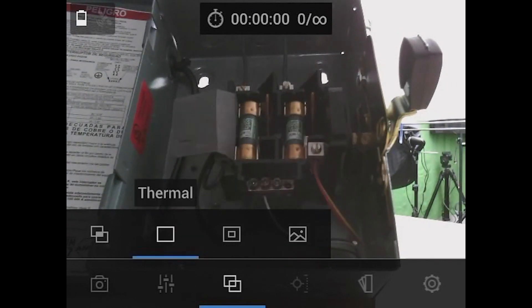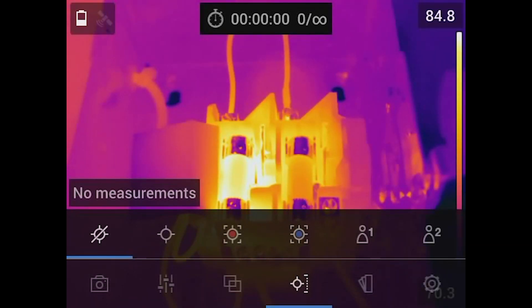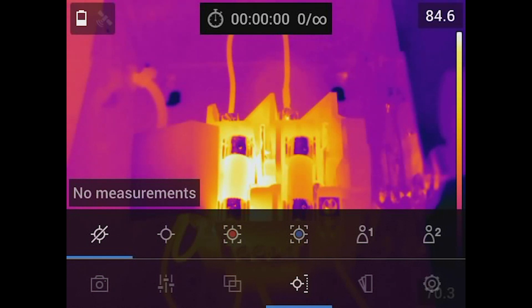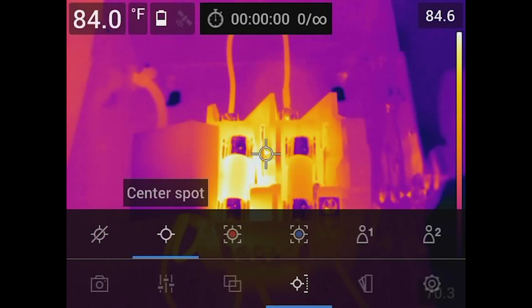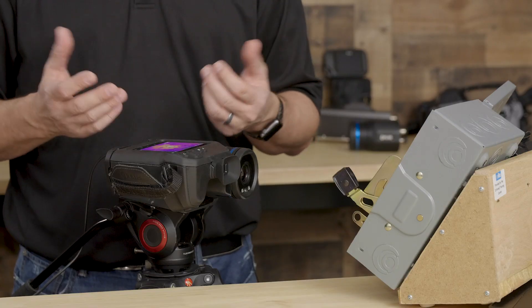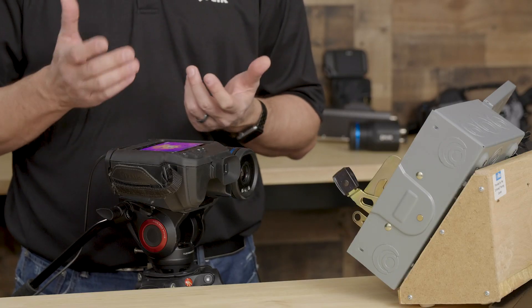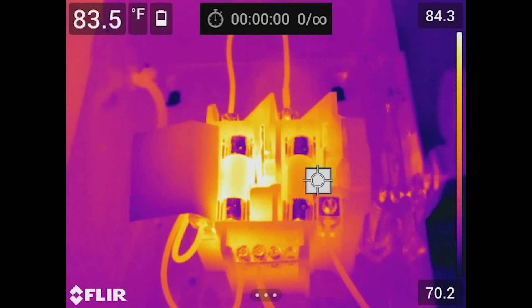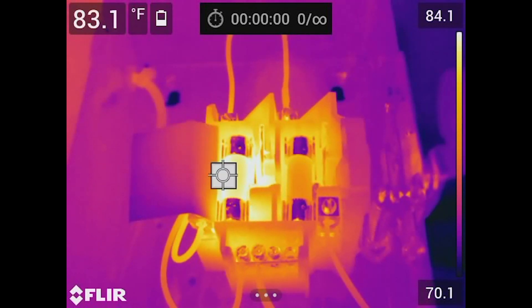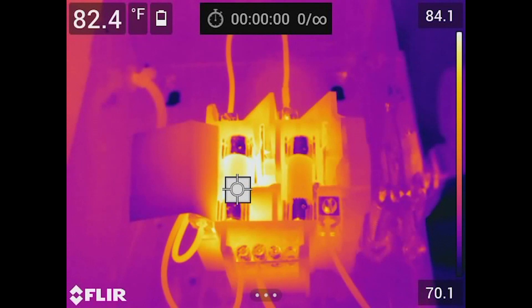As we move back to thermal, we can put some of our measurement modes on the screen. Starting on the left, we have no measurement — so if you had a bunch of measurements on the screen, we can get rid of all those with just one click. Now let's say I want to add a spot. I'll hit spot and it brings up a center spot on the image. With the touchscreen, I can select it and move it anywhere on the image. I'll put it on this fuse — we're reading a temperature of 82.8 degrees Fahrenheit.